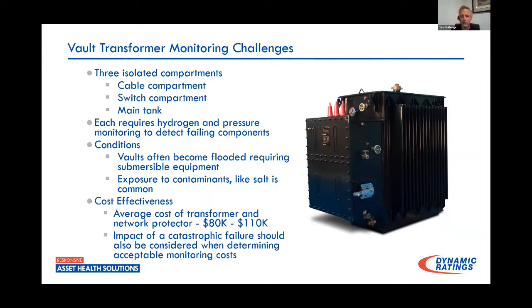But that being said, when you're considering monitoring of these transformers, you really have to take a look at each compartment. This was the problem I was having when I was trying to find monitoring myself: I've seen a lot of online monitoring put in the drain valve of the main tank, the traditional hydrogen monitoring in oil. By doing that, you're missing the cable compartment and the switch compartment completely, because these oils are not mixed at all in these transformers. So anything that were to happen in this cable would not be detected by any type of monitoring on the main tank. The same goes for the switching compartment as well.